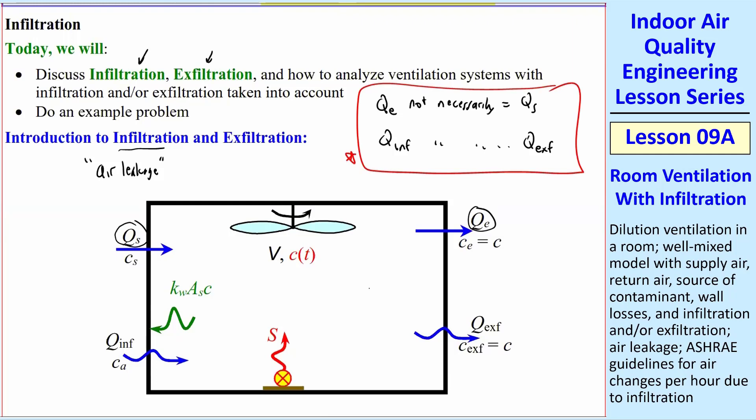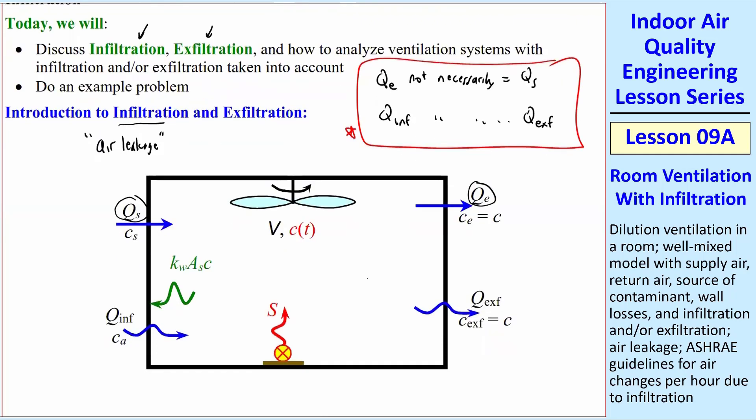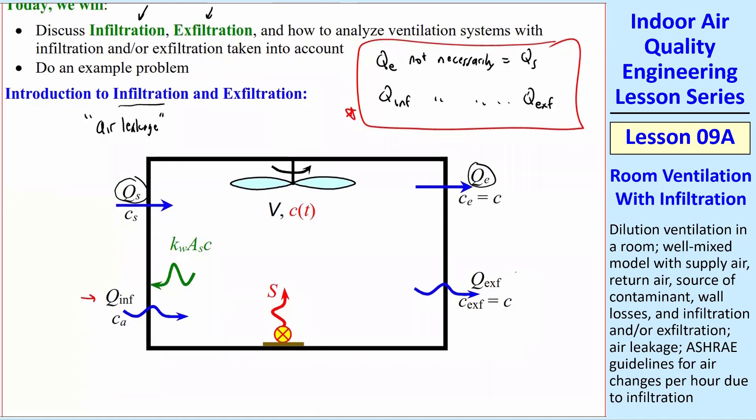For example, if you have a room at a much lower pressure than atmosphere, then you're only going to have Q infiltration. You won't have any exfiltration. If the opposite is the case, you have a high-pressure room, you're not going to have any air coming in from outside, only air going outside. That will be exfiltration.